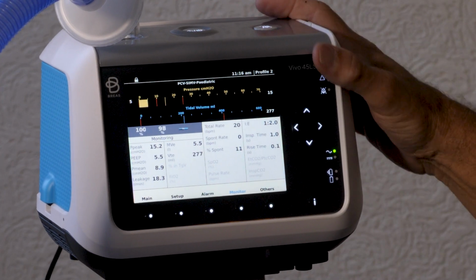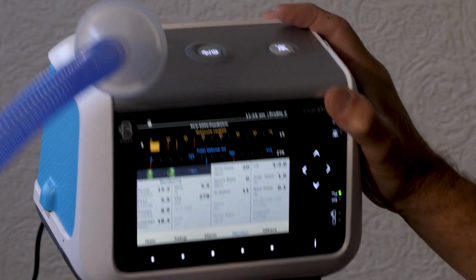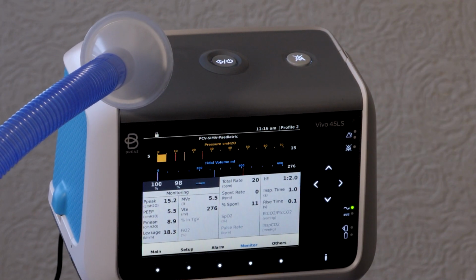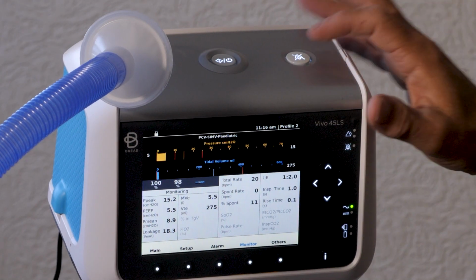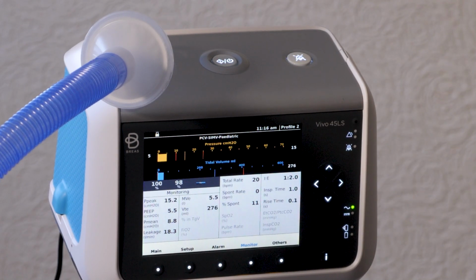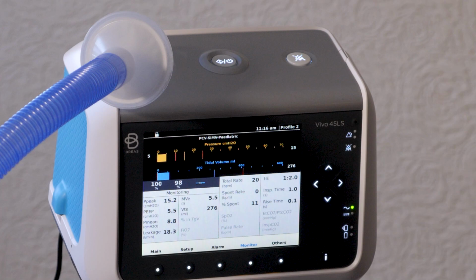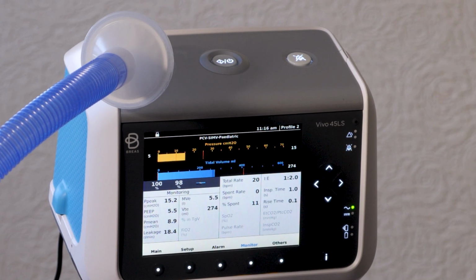So at this time, I also want to mention that you have an alarm silence button, which I think I already did, but it's right up here. So if you're troubleshooting an alarm, you want to hit the alarm silence button, especially at nighttime if you have other people that are sleeping, you don't want to disturb them. Just hit the alarm silence button. It will silence the alarm for 2 minutes. And at that point, you can troubleshoot the alarm without having that audible alarm sounding. Some high priority alarms, you might not be able to silence it for the 2 minutes, but it's going to continue to alarm during some particularly high priority alarms.